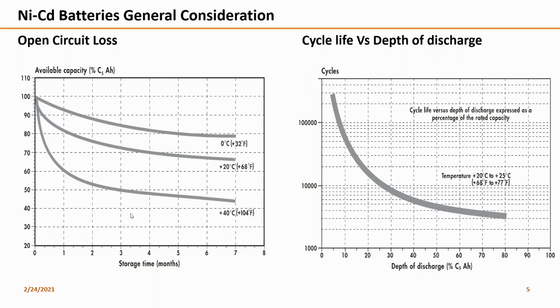The available storage capacity decreases as temperature increases, and it performs very well at normal temperatures. As I said, nickel cadmium batteries have much higher open circuit loss because the internal resistance is much higher than lead acid batteries.